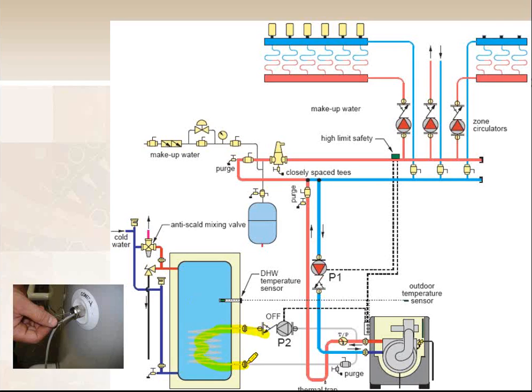And there's a few municipalities that will require you to do that. City of Chicago being the most famous of them, obviously. So if you're doing a City of Chicago job, you're going to have to put a double wall heat exchanger in. You won't get quite as good heat transfer, which means you have to run your boiler a little bit more to get the transfer. But it's still way, way, way more efficient than a 50%, 60% efficient standard water heater.